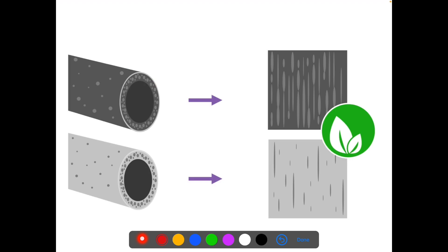Now coming to the composition of the fibers. The fibers can be divided into non-synthetic or synthetic. Non-synthetic can be unmodified or modified. Unmodified means cellulose — non-synthetic cellulose fibers. Modified means the hydroxyl group of cellulose is removed and replaced by any other compound. Synthetic generally comprises polysulfone, polyethersulfone, and PAN-derived — that is polyacrylonitrile. These are the various materials used to make the dialyser membranes.